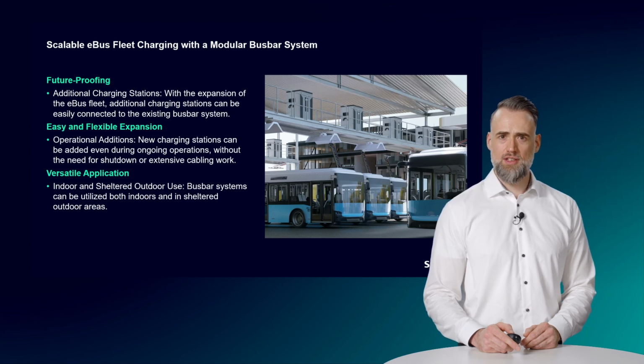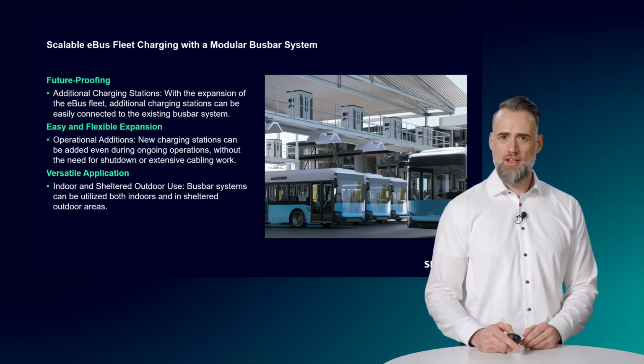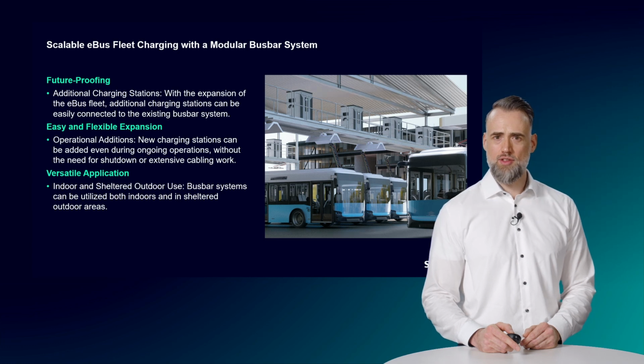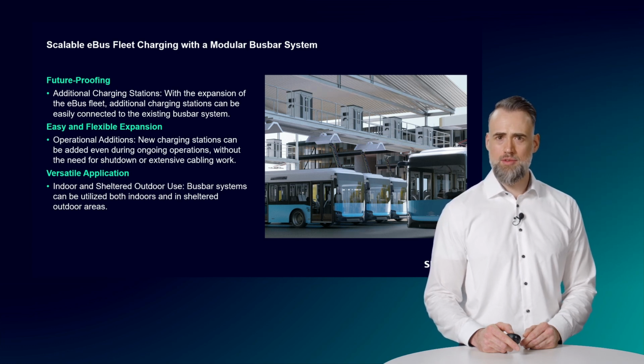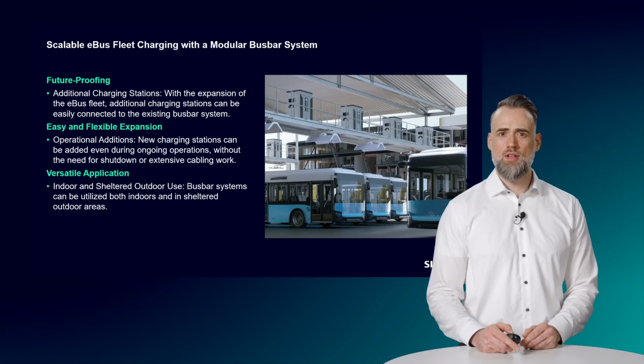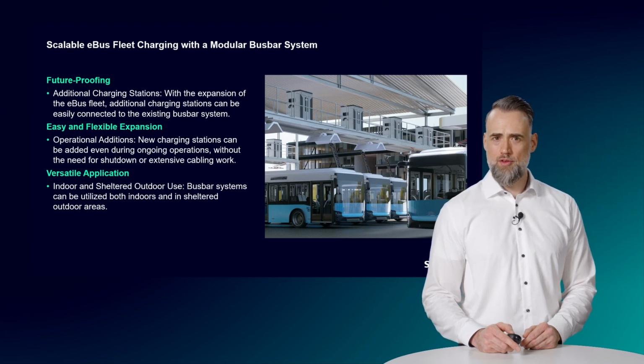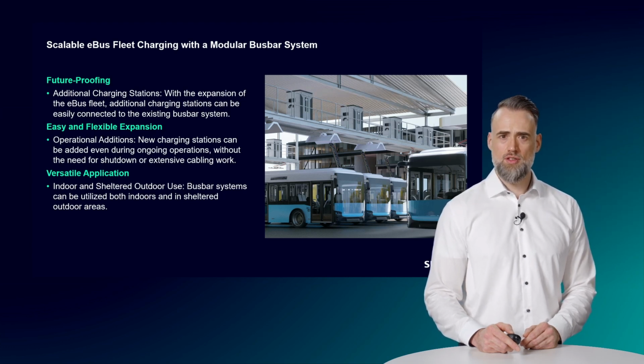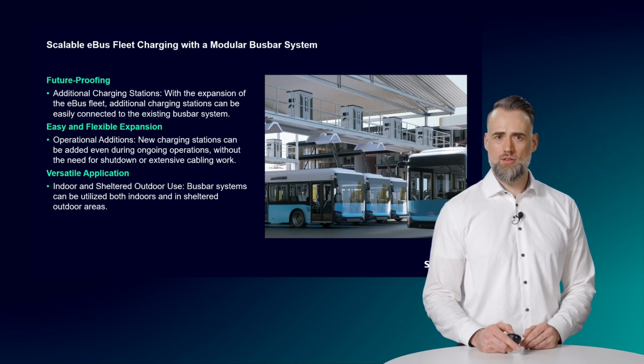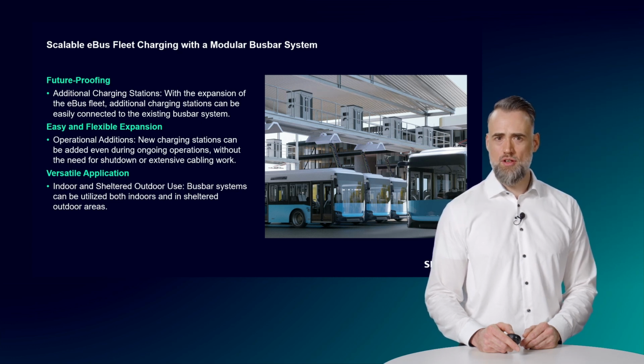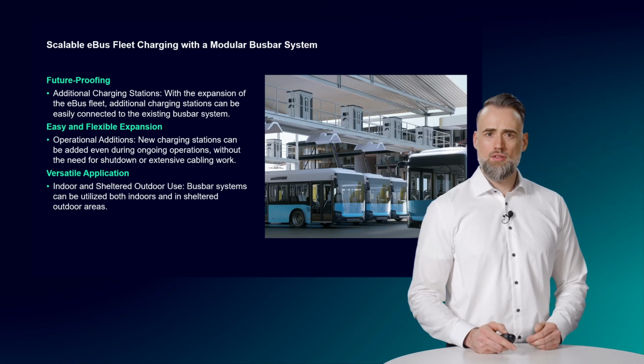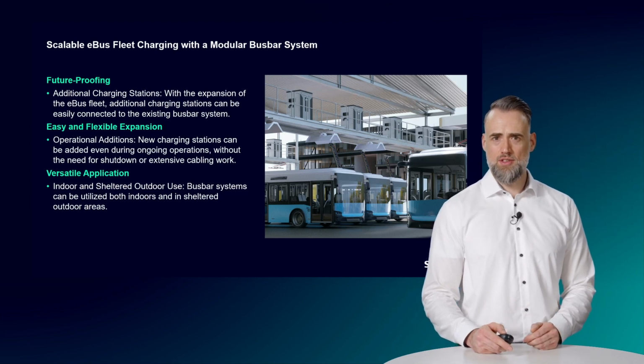This can even be done during operation. Neither a shutdown or expansion of the distribution nor complex cable installations are necessary. Simply put on a new tap-off box with integrated protection switching device, connect it to the charging station and switch it on. That's it. Did you know that busbar trunking systems can be used indoor and outdoor, protected from the weather?